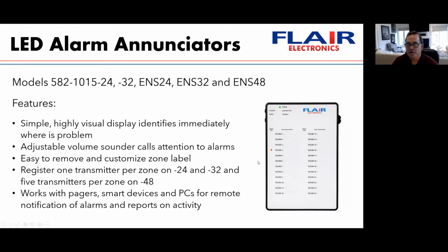Features: these alarm panels are super simple with highly visual displays identifying immediately where there's a problem. Unlike a little alarm panel or a computer, guards or caregivers can look at the panel and immediately know where the issue is. There's an adjustable volume sounder on the right side that calls the attention of guards or caregivers that there's a problem. The zone label is a paper template underneath a plexiglass cover, easy to remove, and it's actually a Word document you can customize for your particular application.